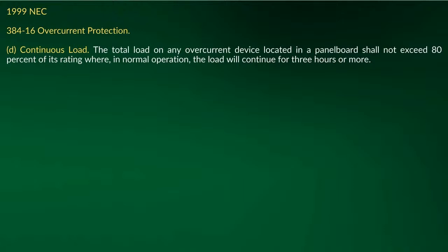But when you look at the continuous load here, and it talks about overcurrent protection, it says the total load on any overcurrent device located in a panelboard shall not exceed 80% of its rating, where in normal operation the load will continue for 3 hours or more. So that's basically telling you this is a continuous load. So if I take a 20 amp breaker at 80%, that's going to give me 16 amps. If I take 16 amps times 125%, that's going to give me 20 amps. So basically the reciprocal of 80% is 125%.